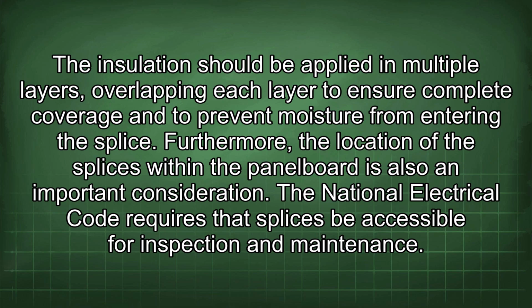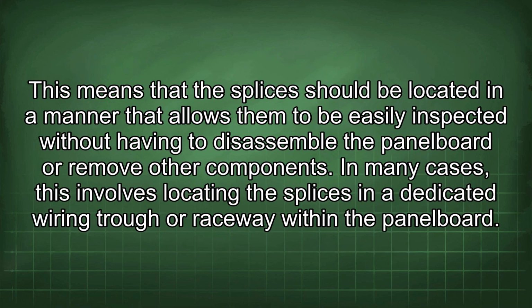Furthermore, the location of the splices within the panelboard is also an important consideration. The National Electrical Code requires that splices be accessible for inspection and maintenance. This means that the splices should be located in a manner that allows them to be easily inspected without having to disassemble the panelboard or remove other components. In many cases, this involves locating the splices in a dedicated wiring trough or raceway within the panelboard.